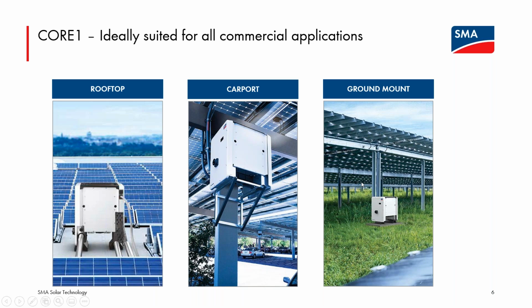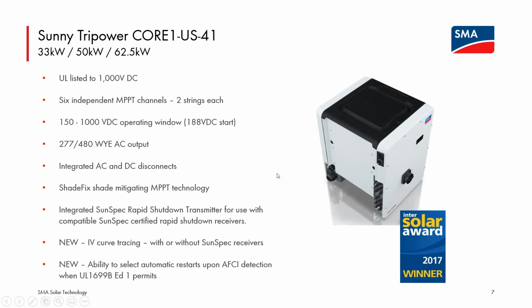So while the focus was commercial rooftop, there is wide applicability for this device. As it is a commercial inverter, it is rated up to 1,000 volts DC. The CORE1 US-41 line, when we launched this product, was only a 50 kilowatt product. And if you are familiar with SMA offerings outside of areas where UL listing is important, IEC listing, say in Europe, it is only a 50 kilowatt unit. When we revved from the 40 launch number to the 41, we introduced the 33 kilowatt and the 62.5 kilowatt units as well. So those are UL listed, all three power classes.